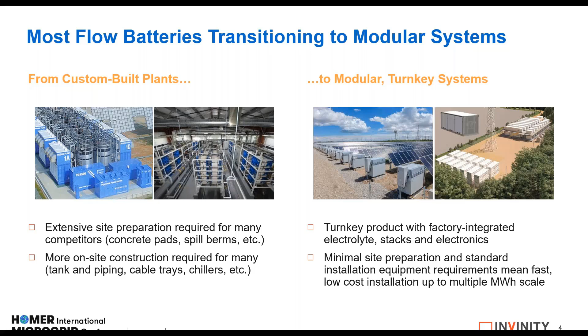The other interesting development in flow technology is that vanadium flow batteries are spearheading the move towards safer, and in particular non-flammable, energy storage technologies. While lithium batteries do manage the risk of fire and explosion with additional system components, vanadium flow batteries simply eliminate that risk. Due to their non-flammability, Invinity's VFBs were recently exempted from the flash ignition test otherwise required for UL's 9540A energy storage system certification.